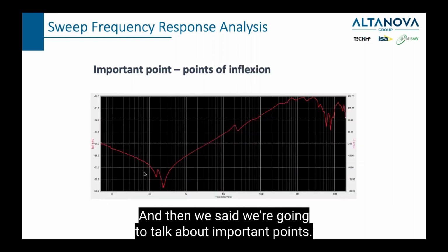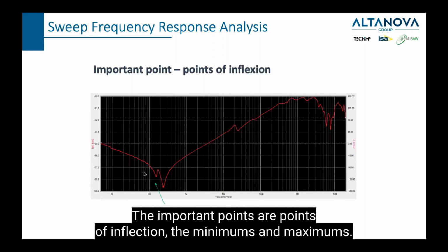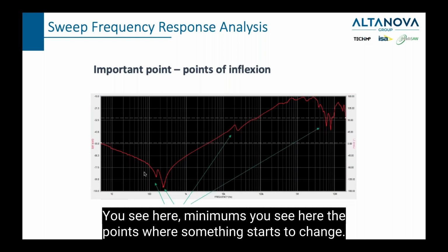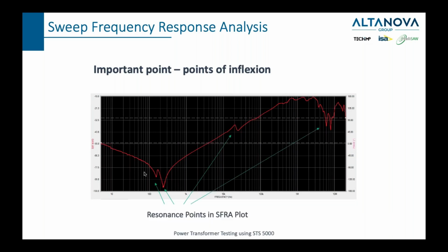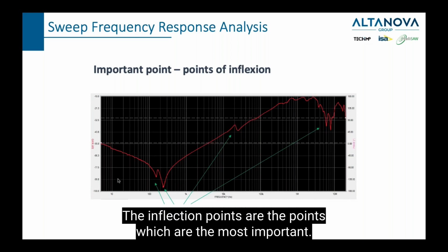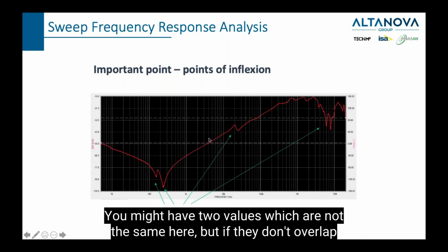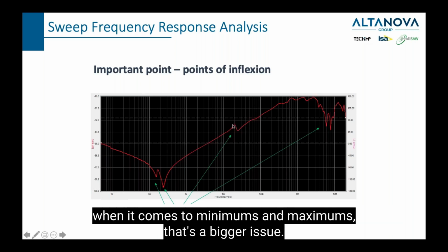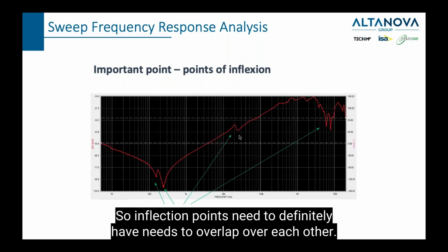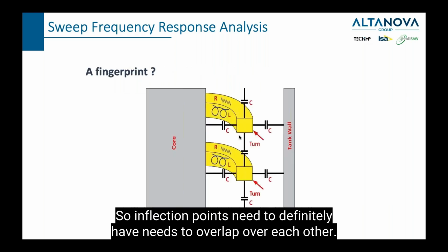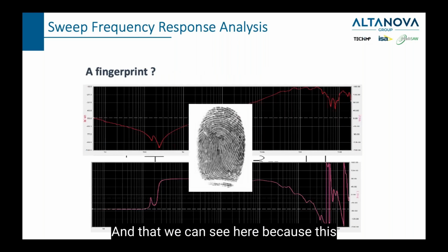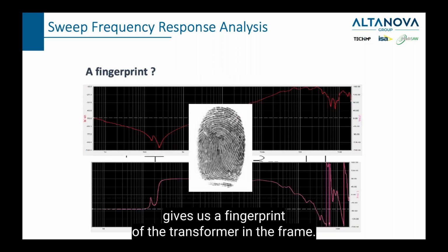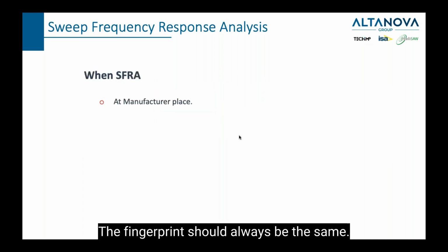And then we said we're going to talk about important points. The important points are points of inflection, the minimums and the maximums. You see here minimums, you see here the points where something starts to change. The inflection points are the most important. You might have 2 values which are not the same here, but if they don't overlap when it comes to minimums and maximums, that's a bigger issue. So inflection points need to definitely overlap over each other. And that we can see here, because this gives us a fingerprint of the transformer, and the fingerprint should always be the same.